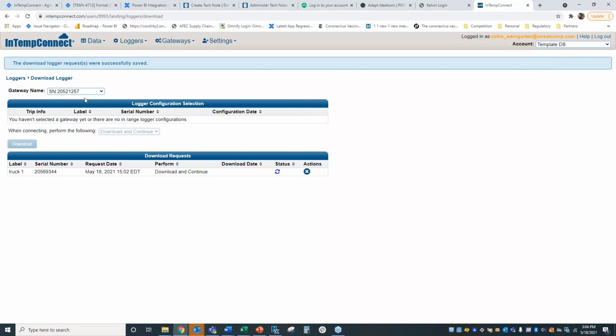Download and restart is typically for storage customers. You have to think about your internal process to see what makes sense, but I usually recommend download and restart for storage customers so you get an additional level of automation. Meaning, if you have to submit a report to the CDC every week, the gateway will download the logger every week and then restart it so the data starts fresh, giving you one week's worth of data every week. You're clearing all that data and having the logger start up automatically, so nobody has to be on site to download it or reprogram and restart the logger.